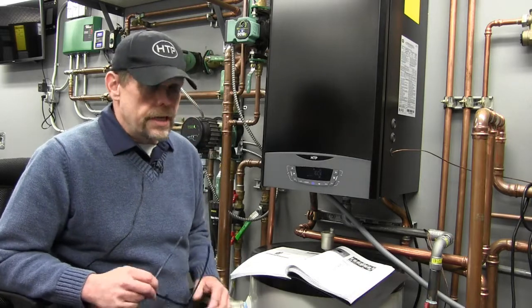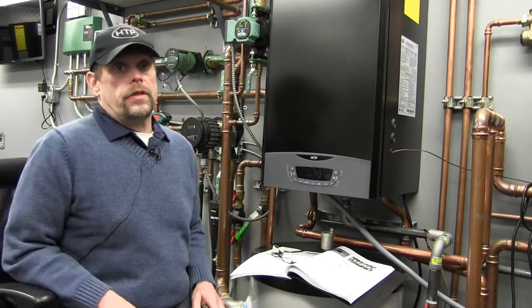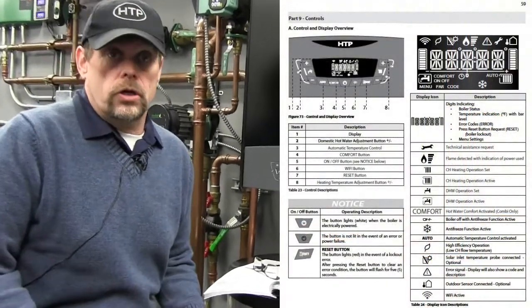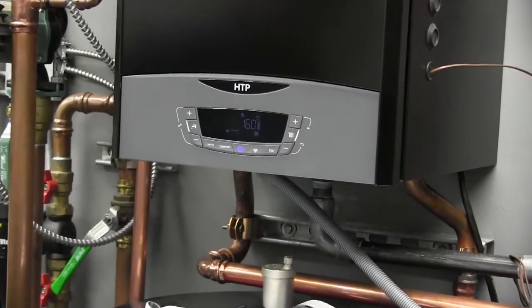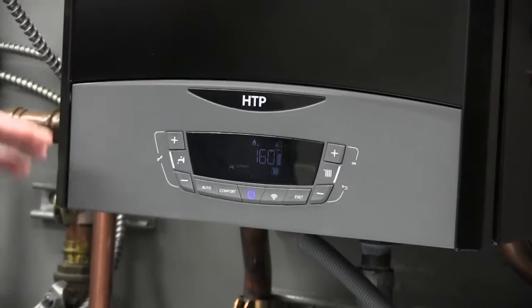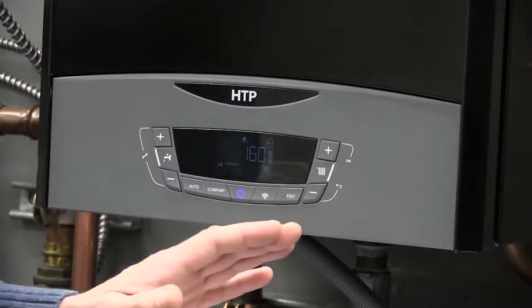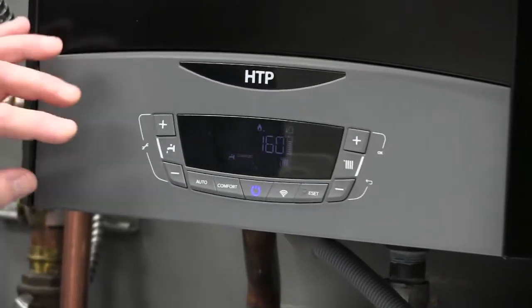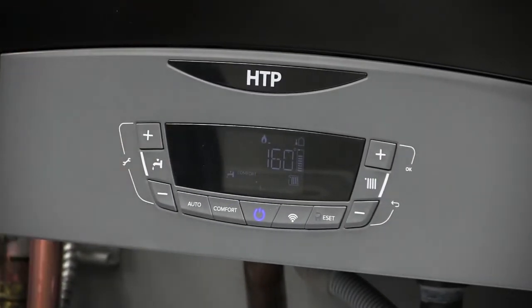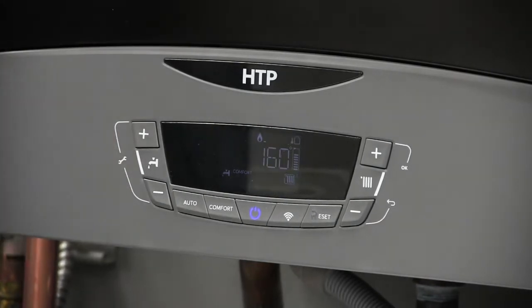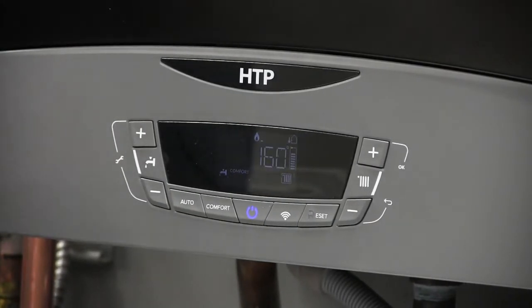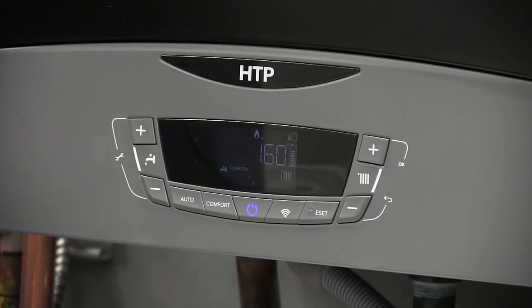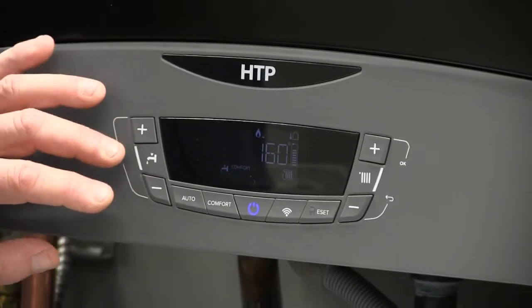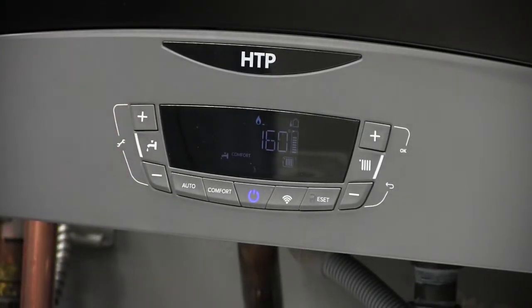Before we dig into the actual menu items, I think the first thing we should do is become acquainted with the actual control panel. The symbols, the buttons, what they mean, what they do. So what I'd like to do is start right here on the control panel. We can move left to right. The first thing we see is a plus and minus button with a hot water faucet symbol. If this were a combi boiler, this is our domestic hot water control. We can raise or lower the output temperature of the hot water by pressing the plus or the minus button.